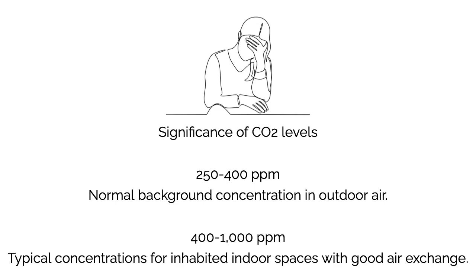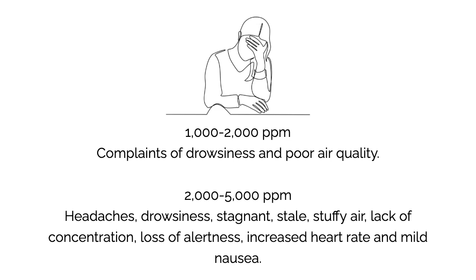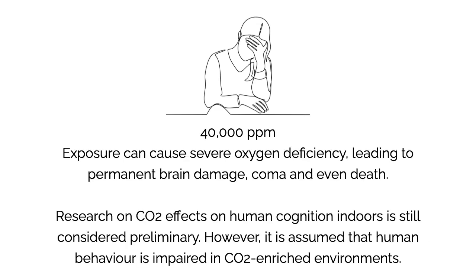Significance of CO2 levels: 250–400 ppm is the normal background concentration in outdoor air. 400–1,000 ppm represents typical concentrations for inhabited indoor spaces with good air exchange. 1,000–2,000 ppm brings complaints of drowsiness and poor air quality. 2,000–5,000 ppm causes headaches, drowsiness, stagnant and stuffy air, lack of concentration, loss of alertness, increased heart rate and mild nausea. Exposure at 40,000 ppm can cause severe oxygen deficiency, leading to permanent brain damage, coma and even death.